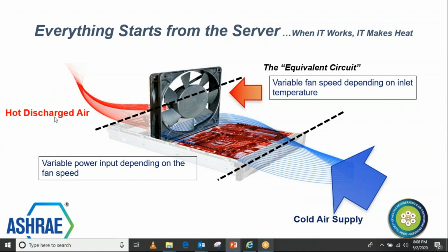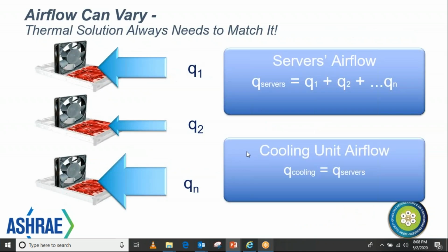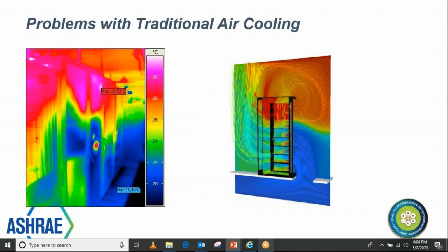And then how efficiently you are able to bring back the hot air to the cooling equipment will overall decide the efficiency. Now, this is in the data center space, or even in any load calculation, you have to match the overall load to the cooling capacity required, and then obviously the room capacity and those things to be added, the fan loss and those things.